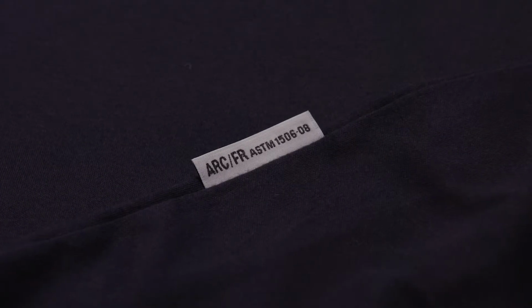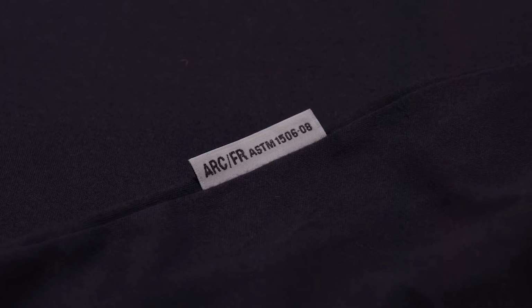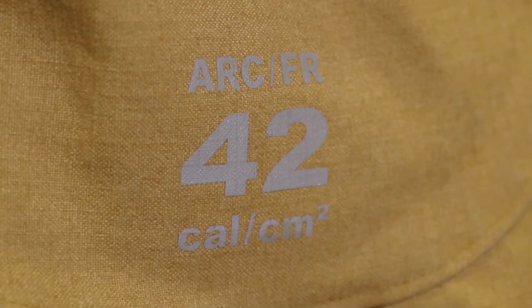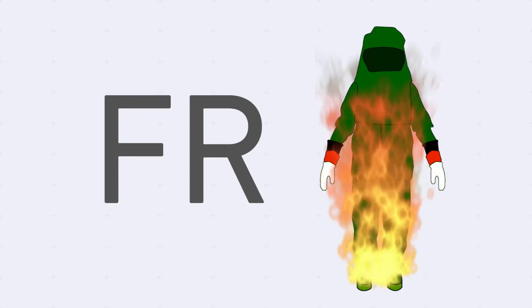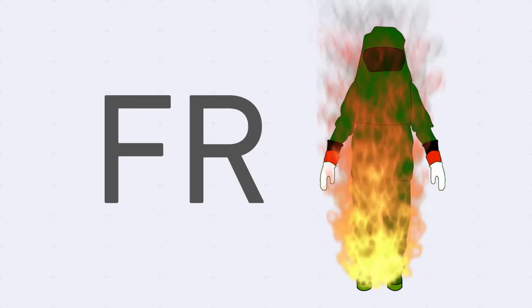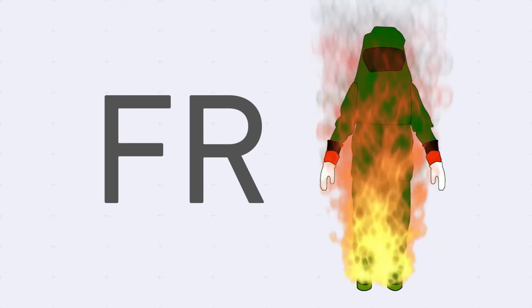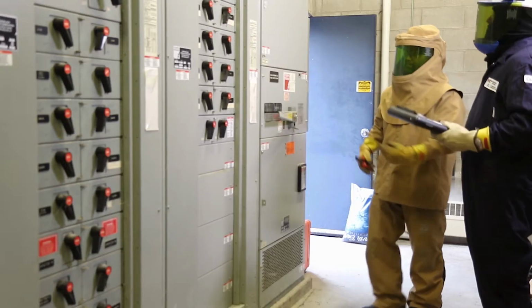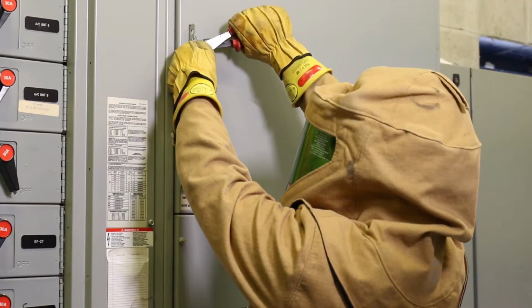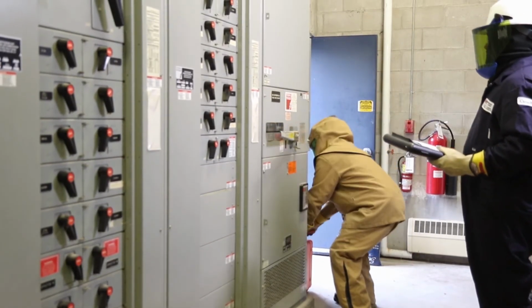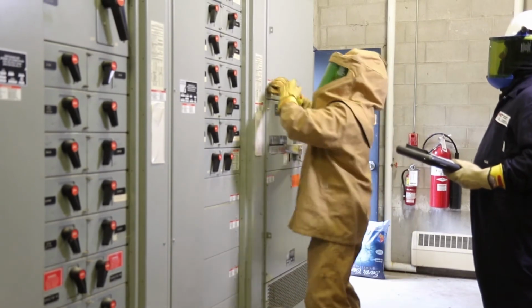It's important to note that while all arc-rated or AR clothing is flame-resistant or FR, not all flame-resistant clothing is arc-rated. All Measurement Canada arc-rated PPE purchased and worn for electricity metering installation inspections shall be flame-resistant or FR. Flame-resistant PPE helps protect electrical inspectors from receiving severe burns when exposed to a flame, and is also self-extinguishing when the source of the flame is removed. Inspectors should always be aware of the AF approach boundaries and ensure they do not proceed past the limited zone when performing their inspection procedures.